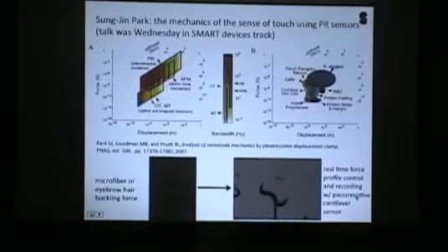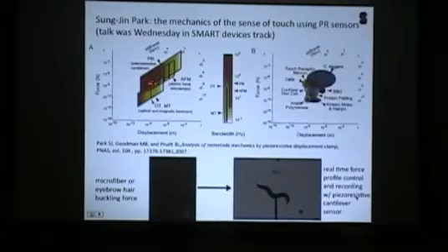The nice thing about piezoresistors and why we settled on them, even though I do like piezoresistive cantilevers, we weren't necessarily married to the idea of that. I'll show you some other things that we do in our labs. So we use electrostatics, we do use polymer sensors. But piezoresistors cover a really large range of force with a single dynamic range, meaning their resolution and their maximum force can cover, say, 3 orders of magnitude, which is something you can't do with these other methods. So atomic force microscopy, yeah, you can cover a large range with it, but you have to change the cantilever for each of these bands to get there. Also, the photodetector in an AFM is not so fast, so we really can't get to kilohertz speeds with that.